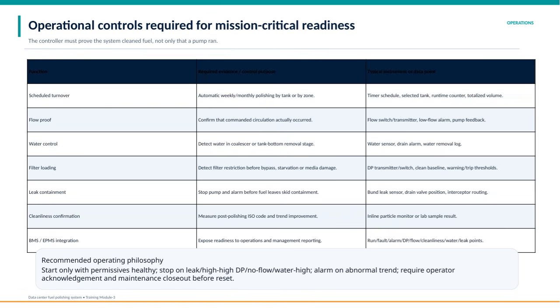provide this early detection. Leak containment stops the pump and triggers alarms before fuel escapes the skid containment area. This is managed with bund leak sensors, drain valve positions, and interceptor routing. Cleanliness confirmation measures and trends the particle count post-polishing, either with inline monitors or lab samples, to verify the fuel meets ISO cleanliness codes. Integration with building management systems or electrical power monitoring systems allows for comprehensive reporting of run status, faults, alarms, differential pressure, flow, cleanliness, water, and leak points, exposing the system's readiness to operations and management.